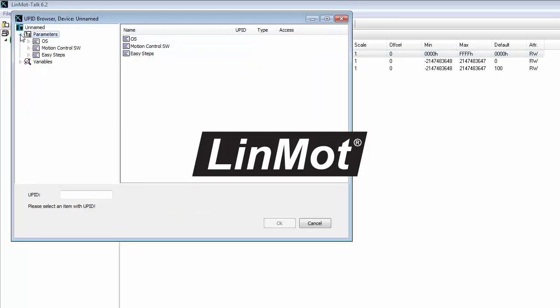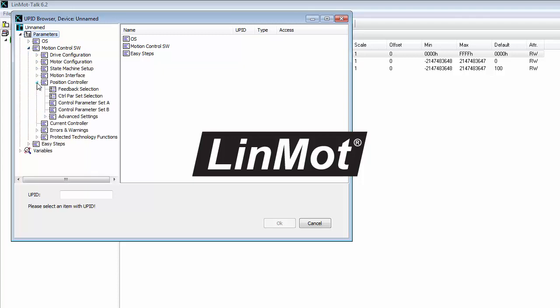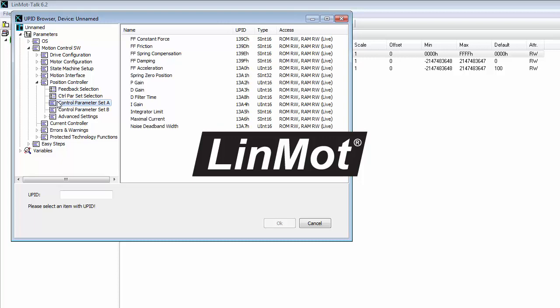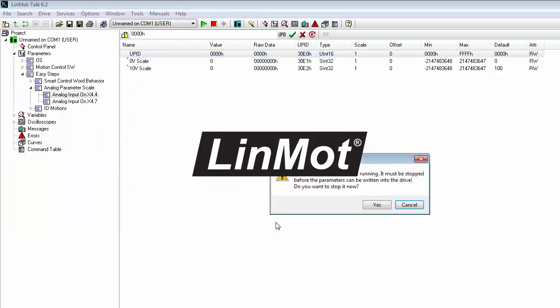We're going to go to Parameters, Motion Control SW, Position Controller, Control Parameter Set A, and pick the maximal current parameter. Notice how the parameter ID shows up down here. We say OK.